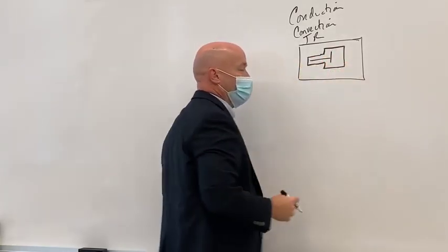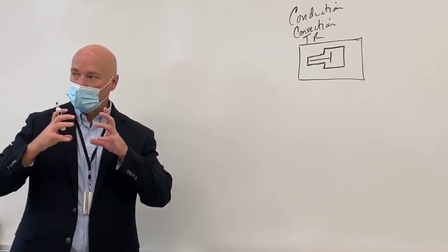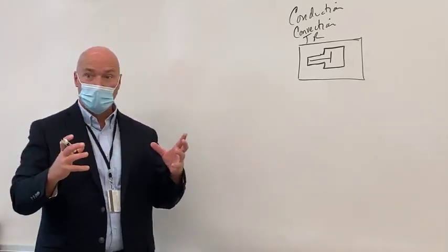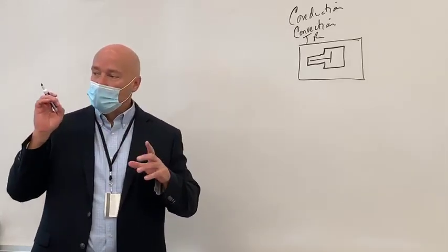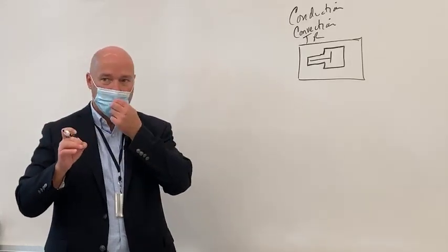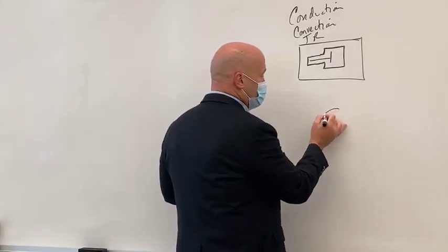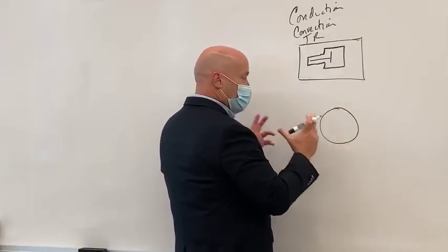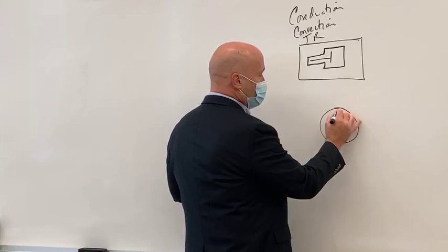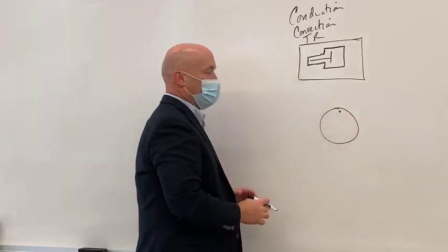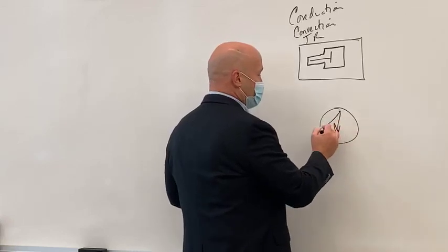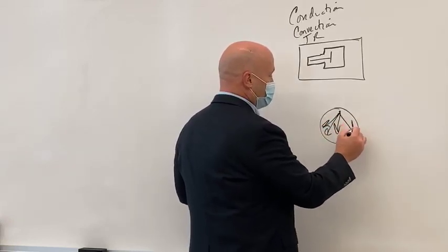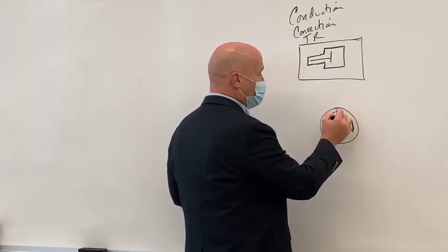Conduction occurs in a couple of different places. First off, we've got a big anode. The anode surface is really large, right? But we only use a very small portion of it at any given time. Looking at the face of the anode, our actual focal spot is only about that big, so it gives the heat a lot of places to go. It can conduct all around the surface so that it removes some of the heat from just that area right there.